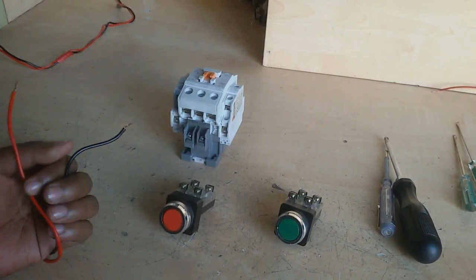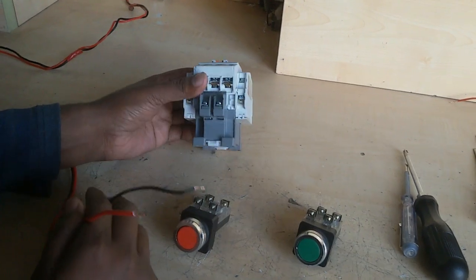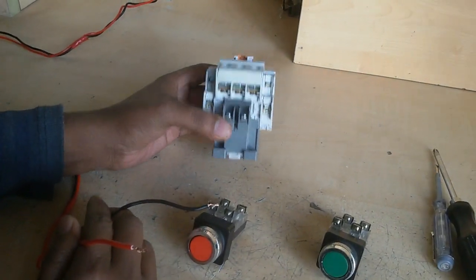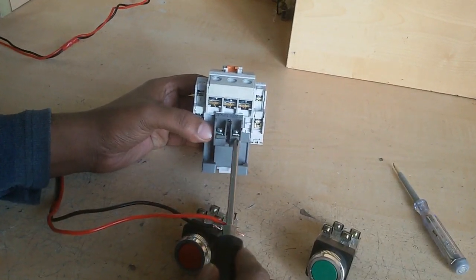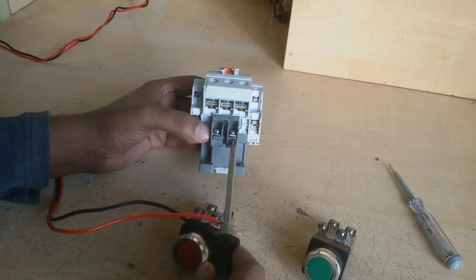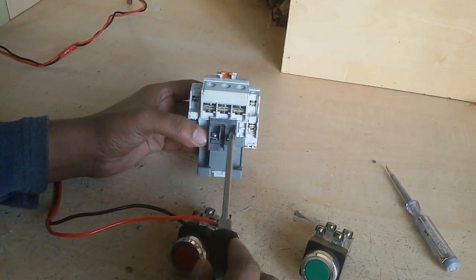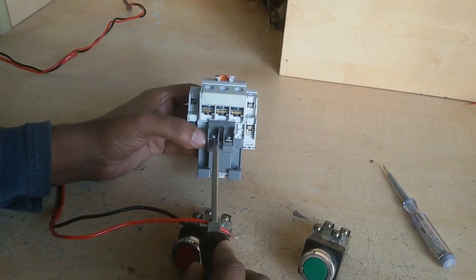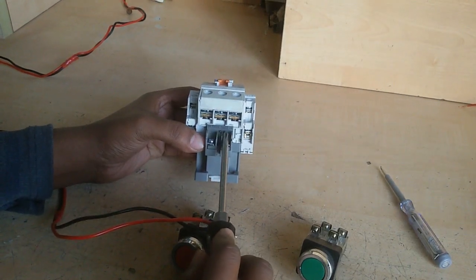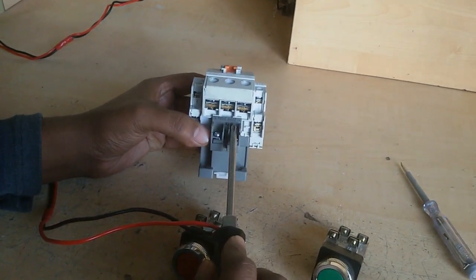Now I connect the neutral into magnetic contactor. This magnetic contactor has a holding coil. This holding coil has two terminals. One is labeled A1 and other is A2. In A1 and A2 terminal need 220 volt AC.